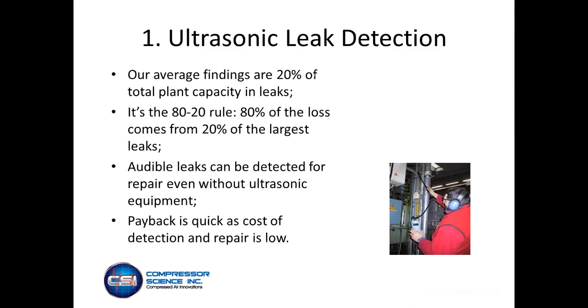Leak detection, again, it's very difficult for a lot of our clients to stay on top of. A lot of older plants especially have a lot of threaded pipe, and it's something they continuously have to stay on top of. It's the 80-20 rule. I tell a lot of my customers 80% of the loss comes from 20% of the largest leaks. And without even investing in ultrasonic equipment, I tell my clients, if you're down on a Sunday or you have a shutdown in the plant, have your millwrights or your maintenance guys walk through the plant, and even if you tag and fix the audible leaks, that's going to be 80% of the loss without having to get into doing ultrasonic.